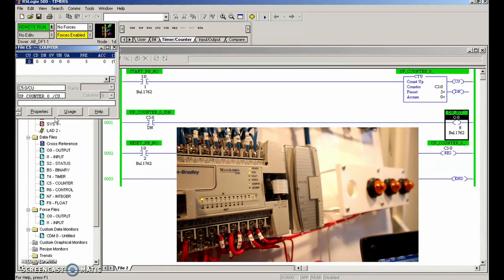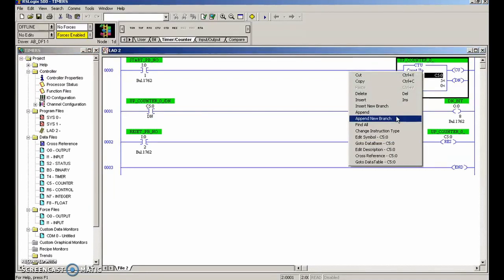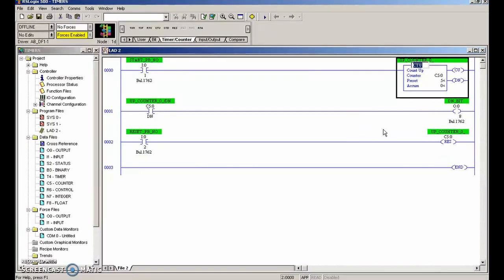Now let's take a look at the down counter. We've gone offline. We're going to change this to a down counter - right-click, change instruction type, use the arrow key to go to the end, backspace, put a D there, hit enter. It's now a countdown counter. We're still going to look at the done bit and still use the reset push button, still addressed as C5:0.